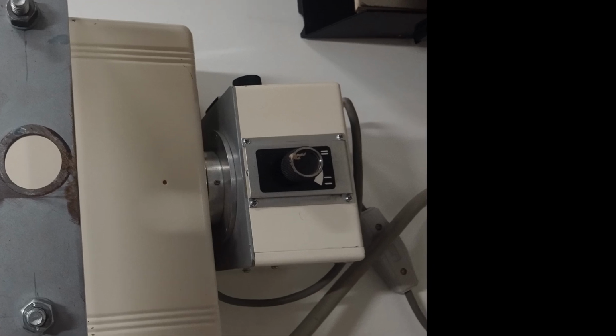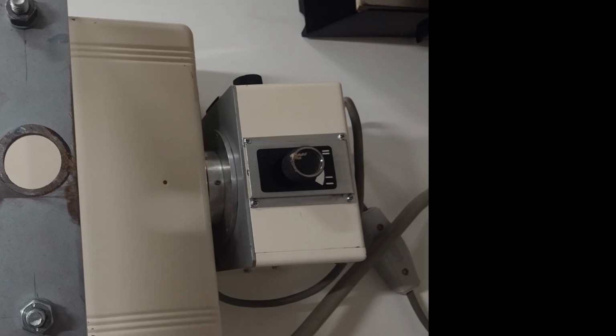Then lastly, at the end of the X-ray source is the beam limiter, or collimator as we call it. This has got lead leaves inside it that can be adjusted with a knob to increase or decrease the area that will be exposed by the X-ray beam. This is usually adjusted so that it just covers the area to be X-rayed, thereby protecting the rest of your patient from radiation.